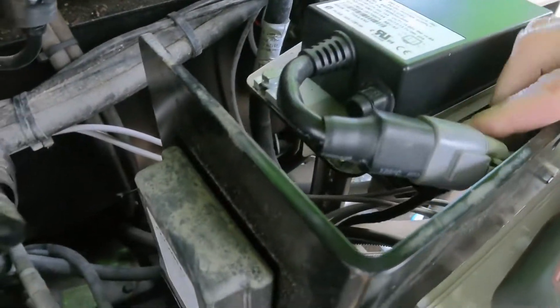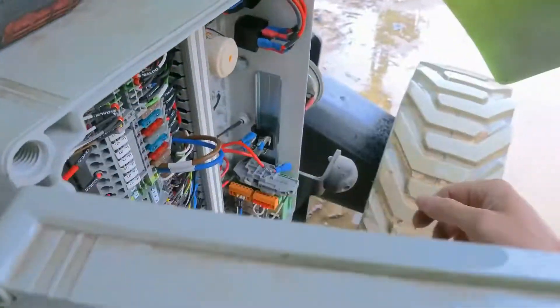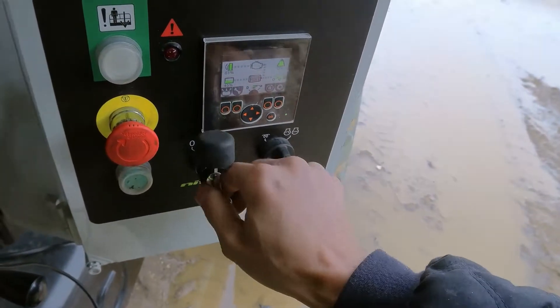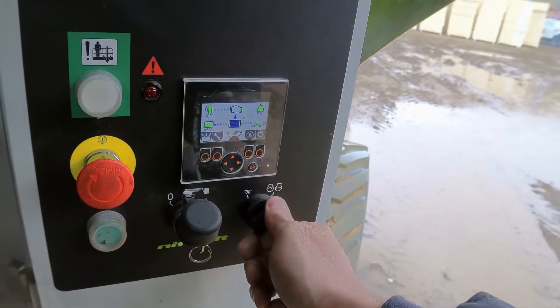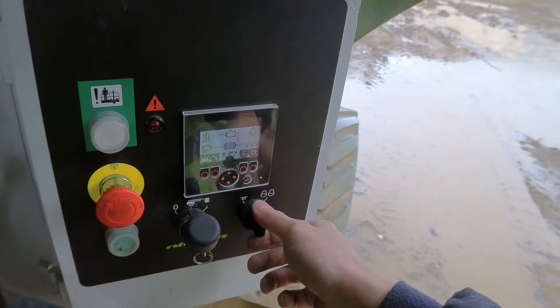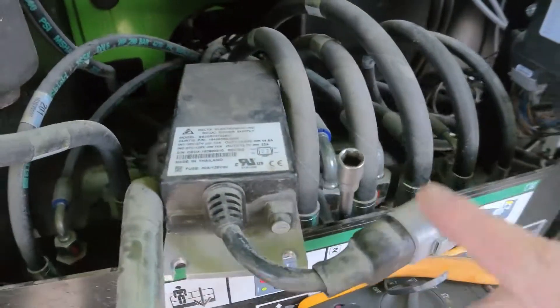I had one in stock — this is the old one. The wiring seems to be okay, no problems there. I've connected the new converter back on now. Let's see if it's going to start or blow the fuses again — one, two, three, go. That seems to be good. I think the problem is this converter.